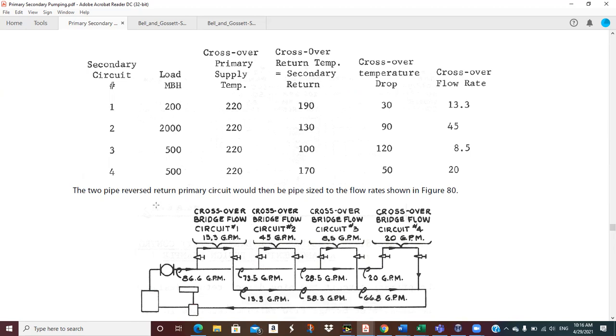Likewise, for secondary circuit number 2, I've got 2 million BTUs per hour, and my overall crossover drop is 220 in, 130 out, so I've got 90. That's going to require 45 GPM. And the last two are the same thing; you just do the math. For number 3, I've got 8.5 GPM, and for number 4, I've got 20 GPM. Let me add those up real quick. I've got 13.3 plus 45 plus 8.5 plus 20. That's 86.8, and that's total GPM, right?